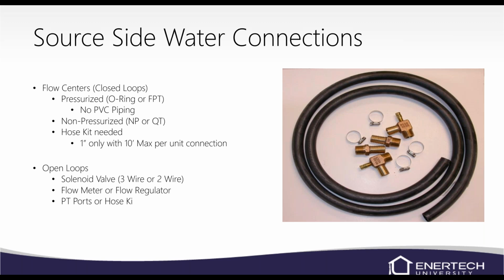And then regardless of whether you have a pressurized, non-pressurized, open loop, closed loop, always make sure you're putting PT ports in. Without pressure temperature ports, there's no way to check for flow. So if you call in tech support and we can't get flow, obviously flow can affect everything else, your refrigerant circuit. So we've got to make sure that we've got proper water flow, and that's what the pressure temperature ports are for. So when in doubt, install a PT port.